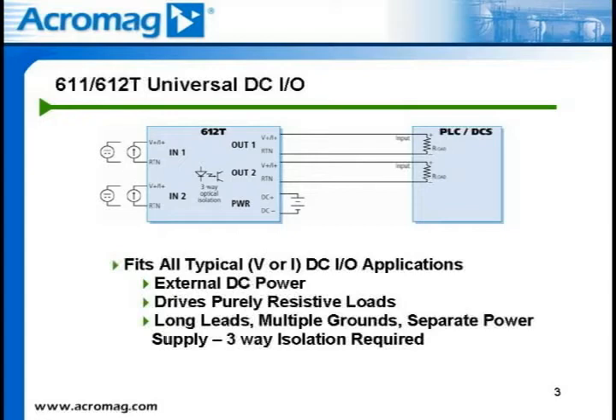The 611T and 612T solve the case of multiple grounds for the input, output, and power circuits by isolating them. The result is a loop tied into a good reference point without having the potential of a ground loop to bring down the process loop. One example is where a field sensor is used as an input to a PLC, and the field sensor obtains power from an external DC source. This source may have a different ground potential than the PLC or field device. If this is the case, the power ground must be isolated from both the input and output.